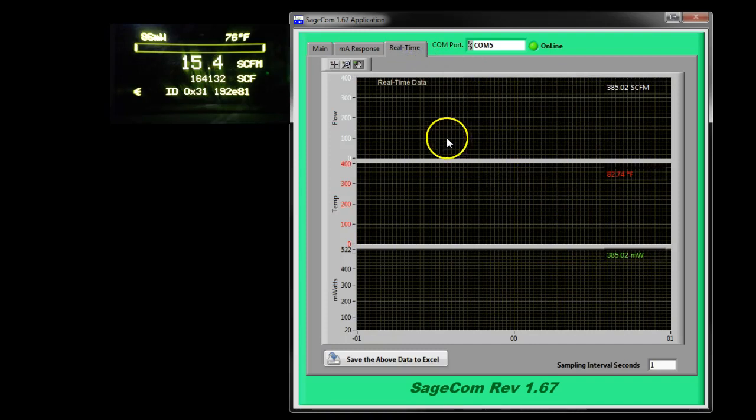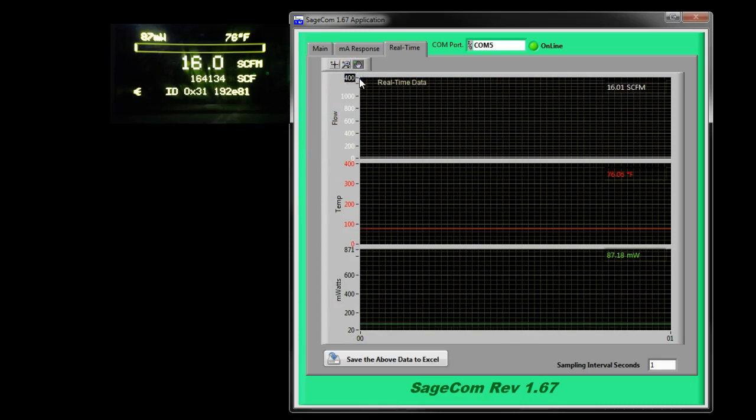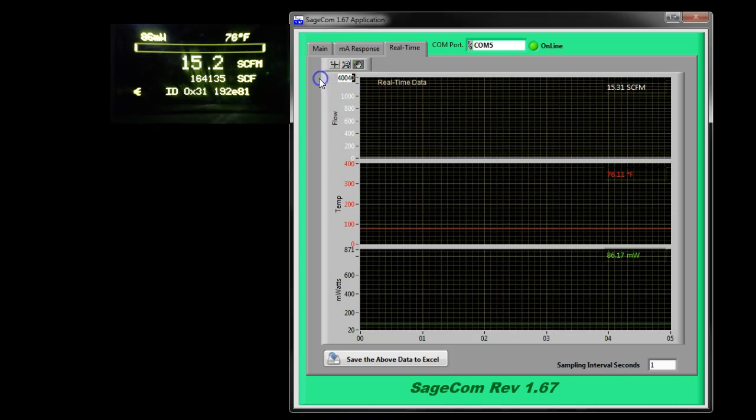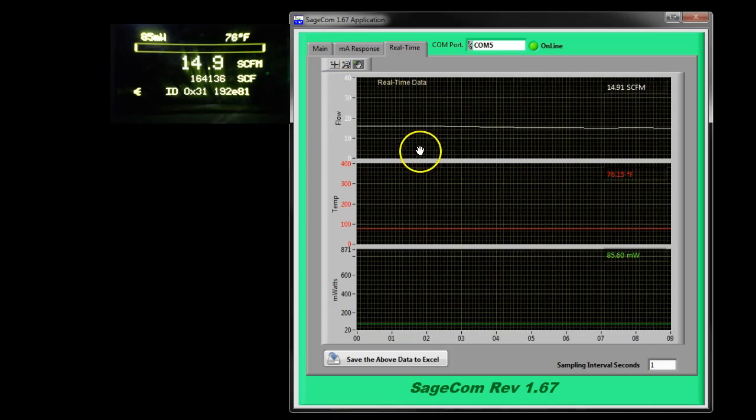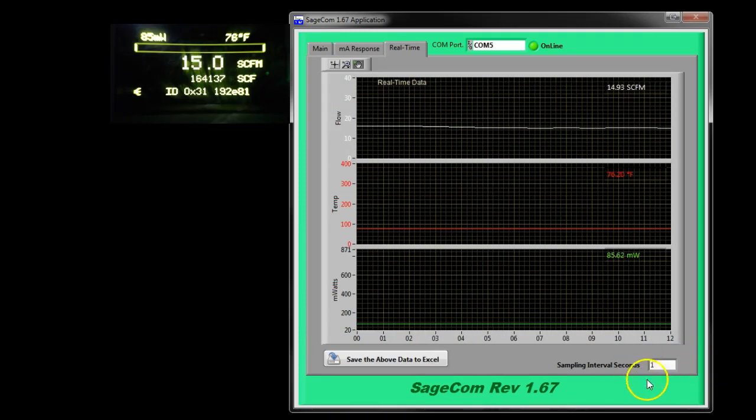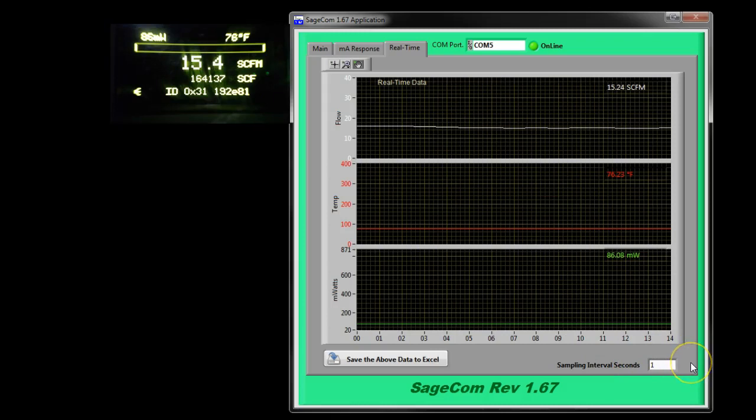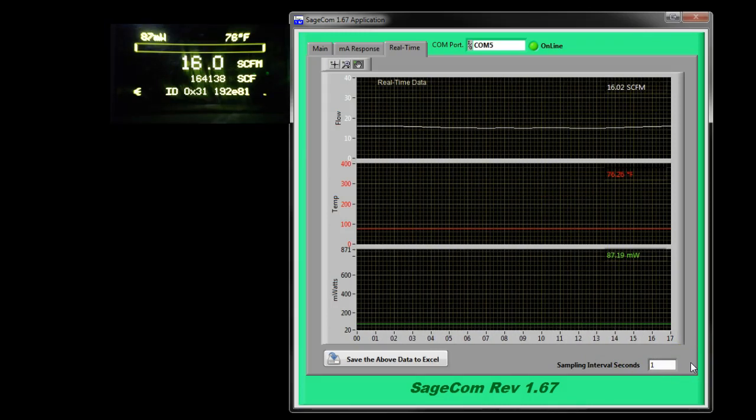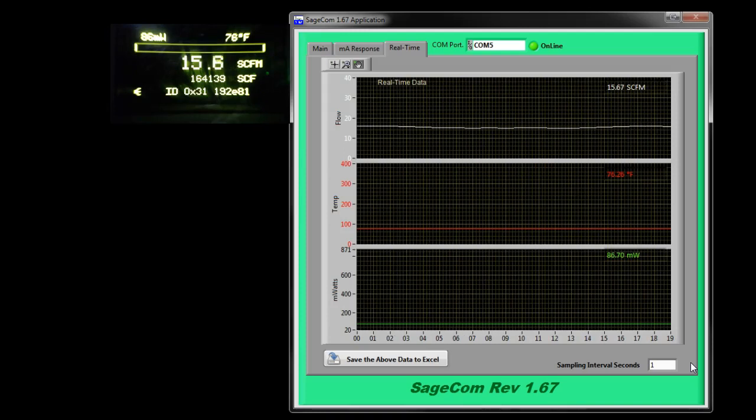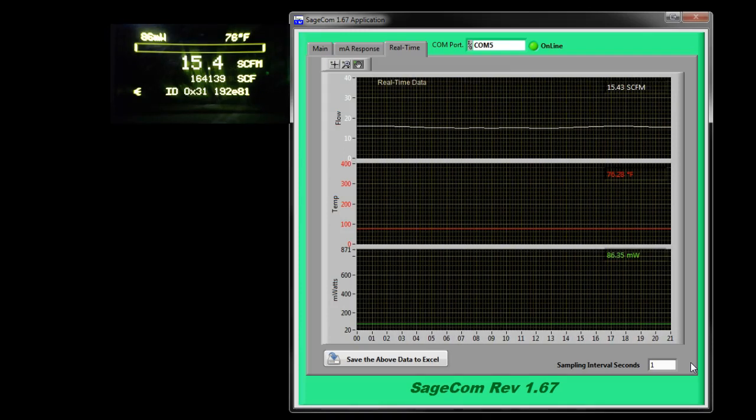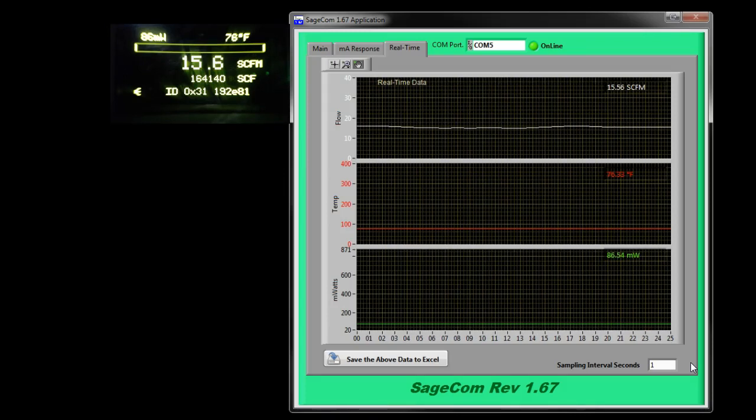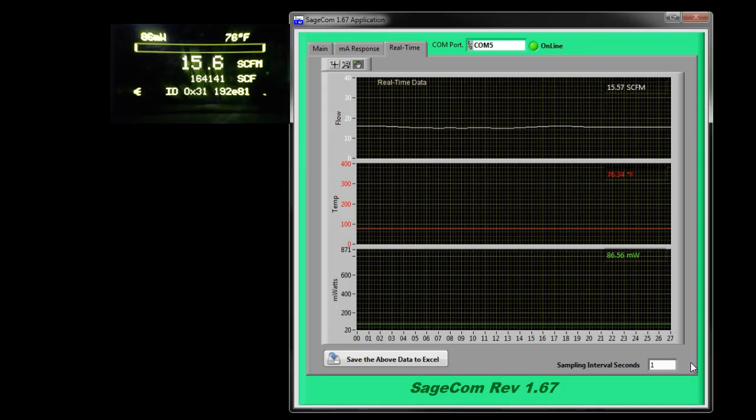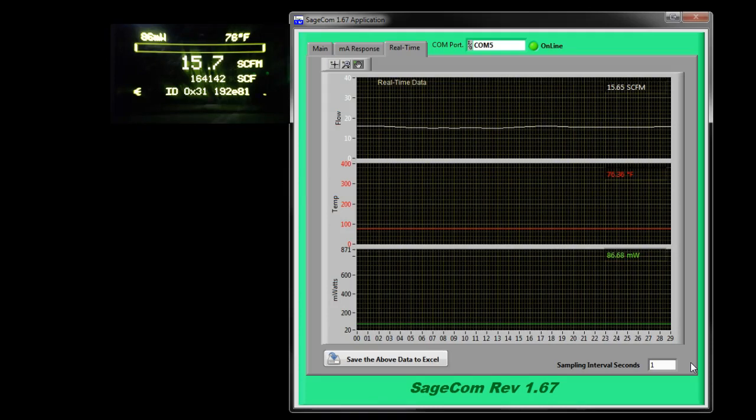Let's go to the real-time menu. Well, I'm only reading about 15 SCFM. So, change the vertical axis here so it's easier to read. Maybe to 40. And notice that you're getting data being logged every second. Now, you can change the sampling interval to 5 seconds or 2 seconds or even 0.1 second. But if you want to data log for a long time it only stores about 65,000 readings. So, use a 5 second or 10 second interval if you want to go for days and days.